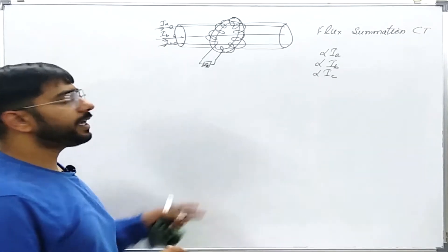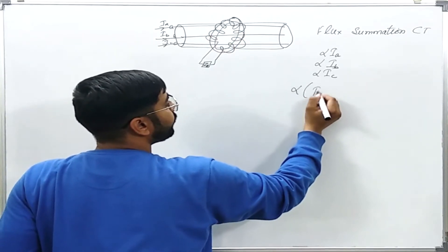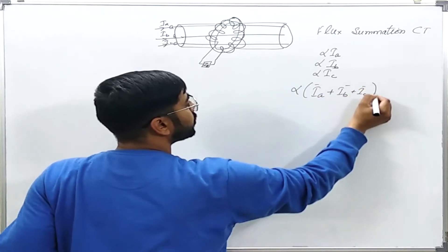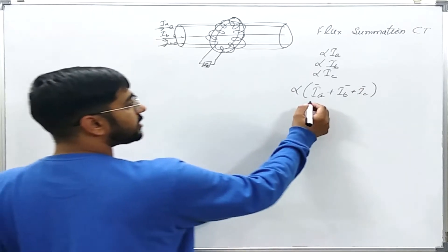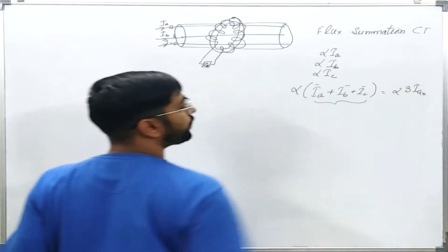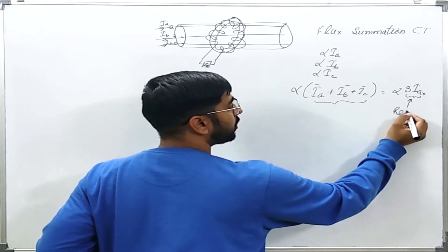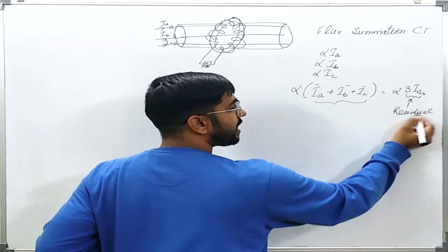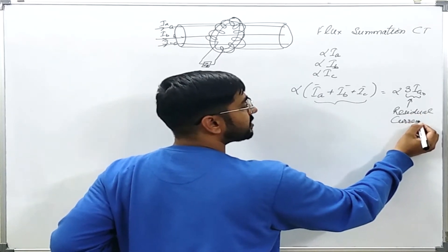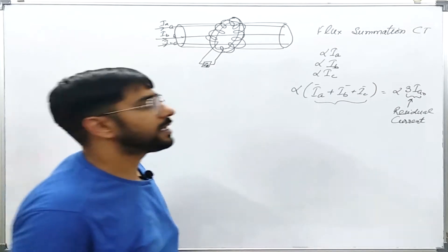The resultant flux in the CT core will be proportional to the phasor sum of IA plus IB plus IC. You see that this is nothing but equal to 3 times IA0. This quantity is usually called residual current. We will see this terminology many times during the study of power system protection. We will also face the term called residual voltage, which is nothing but the similar concept in terms of voltages only.